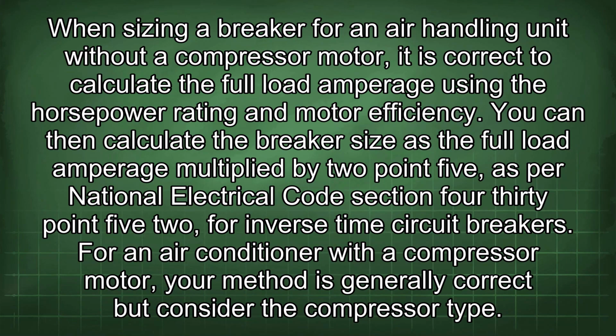When sizing a breaker for an air handling unit without a compressor motor, it is correct to calculate the full load amperage using the horsepower rating and motor efficiency. You can then calculate the breaker size as the full load amperage multiplied by 2.5 as per National Electrical Code Section 430.52 for inverse time circuit breakers.